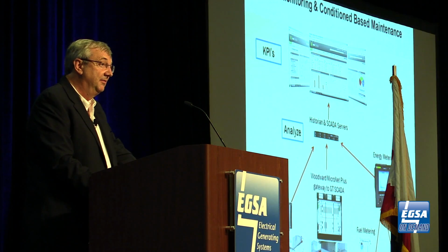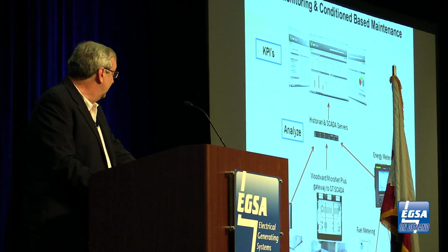You need very accurate energy metering, and that goes into the current transformers and the voltage transformers as well. It's not just the meter, it's the full system. So now you've got a very accurate measurement of your fuel coming into the power plant. You've got very accurate information of the energy going out, how much you're producing, and you know your climatic conditions. Are we compliant with our contract? The reason that's important is if you're paying 16 to 18 cents a kilowatt hour, I'm charging you 4 to 5 cents for the power plant to convert that fuel into electricity.